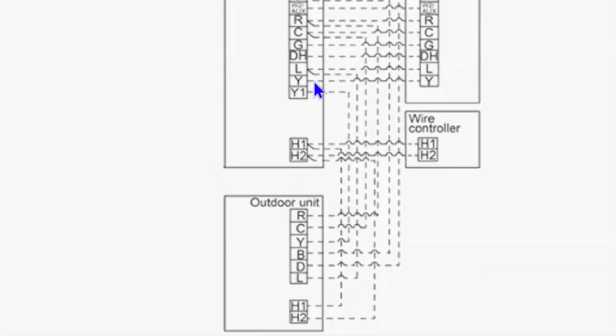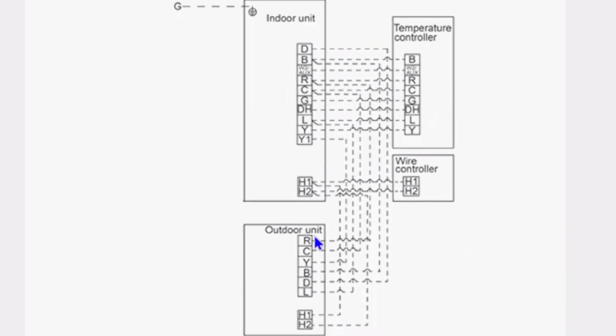What that is for is because this is R32 and it has the A2L alarm in it. If this thing goes into alarm on the indoor unit because of a leak, it is going to break the 24 volts and drop it to the outdoor unit and shut that unit off immediately. The other thing it's going to do is power L.